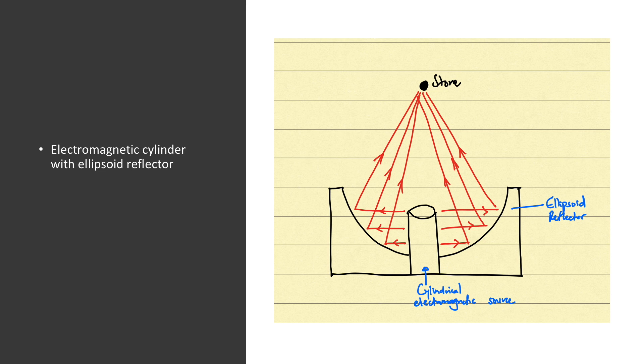The second type of electromagnetic device has the coil in the shape of a tube and the surrounding membrane is cylindrical. The whole cylinder is repulsed by the magnetic field, generating a cylindrical wave, which can be focused by a parabolic reflector, as you can see in this diagram. In both cases, the mechanism of focusing is very reproducible and the variation between individual pulses is minimal — in fact, it can be measured at less than 10%. Therefore, the shockwave energy produced by an electromagnetic lithotriptor is much more consistent than with the EHL device.